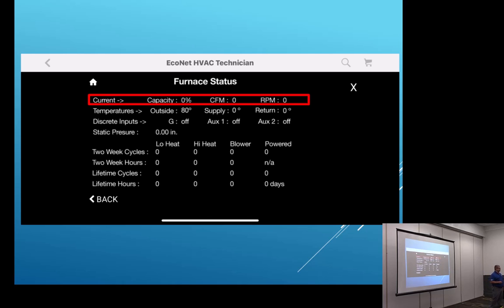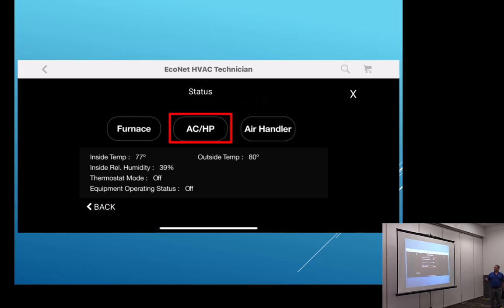What if we've replaced that motor twice in the last 3 years? Wonder why. So if we have this, you say, well, we're moving 1600. I got good airflow, but you're not cooling, right? What's the velocity of that air going across that coil? We want it around 700 feet per minute. It's probably up around 900 or 1,000. So if it's screaming across that coil, we're not staying in contact with that coil. We're not gathering the superheat that we need, right? The coil's getting colder. We don't have the superheat that we need. Now, what are we sending back to the compressor? Liquid that we don't want to send back. And we're going to talk about that later, too. So it all works together. I don't focus just on one piece, but it all works together, guys.